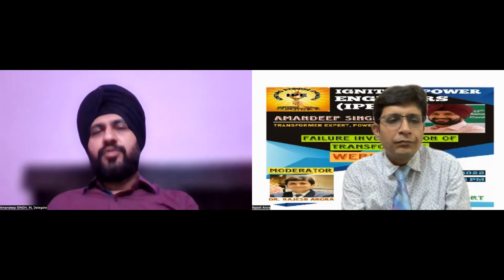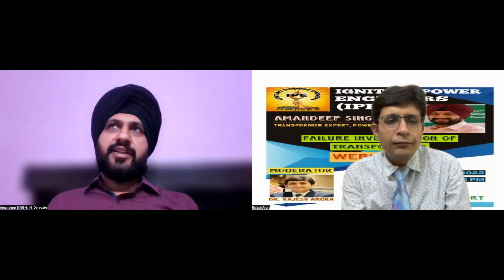Firefighters came, and they just watched and tried to isolate the area from the other locations. But it was extensive damage. Three transformers were gone, and the inside of the building also had a lot of damage because the brick wall provided was not sustainable to the heat. So that's my experience. More than the damage to the transformer, in such cases we have seen damage to the cables also, because all the CT cables and all equipment cables would have to be relaid, which takes even more time, and then end-to-end termination.